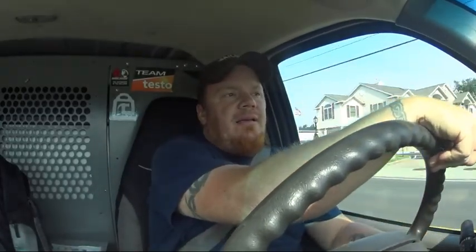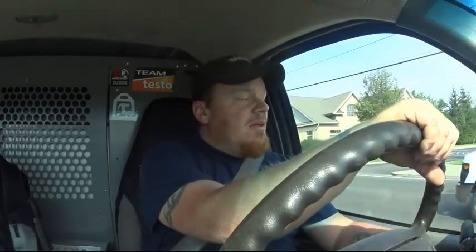I was there Wednesday and the compressor wouldn't start, so I ohmed it out, and I have an open winding. It sounds like the doctor, another doctor's office that we service, didn't realize it wasn't running and just continued to run it and run it.